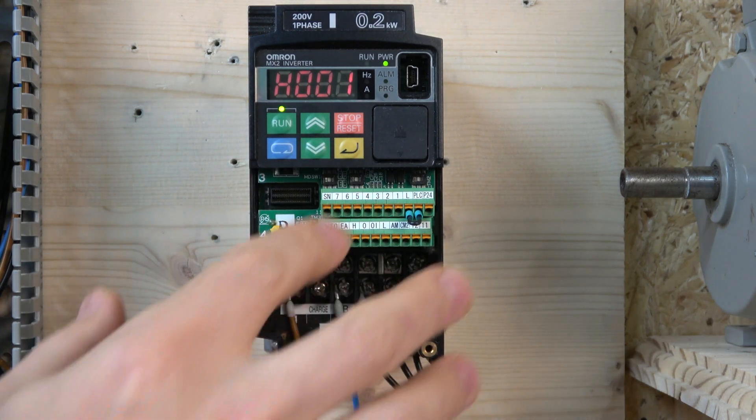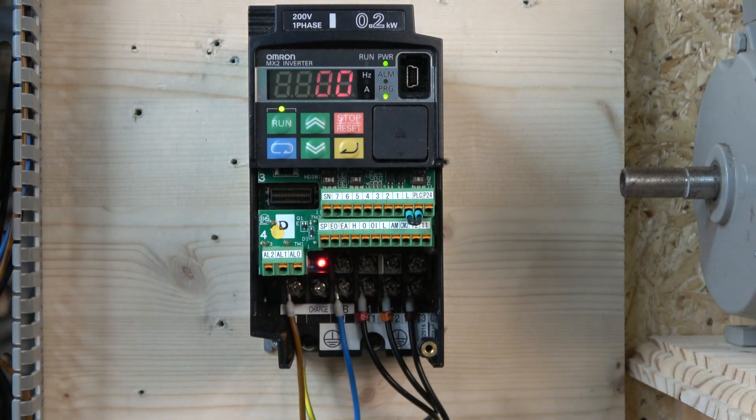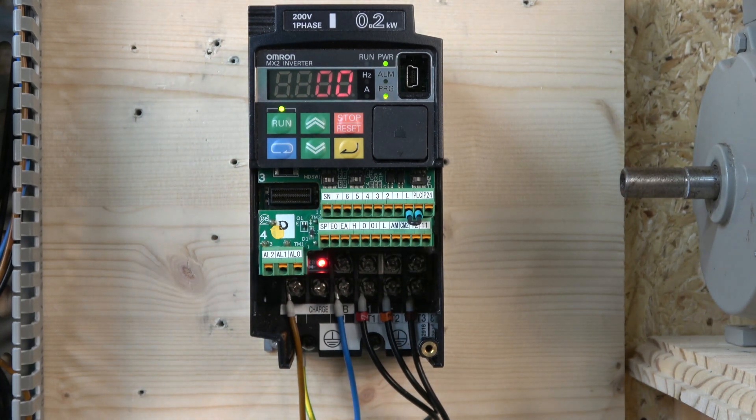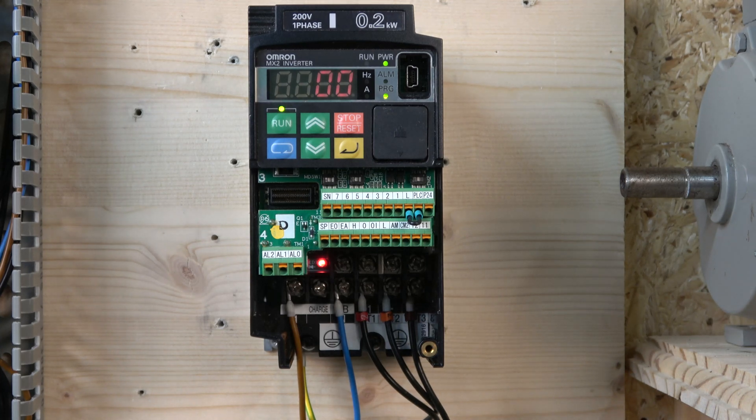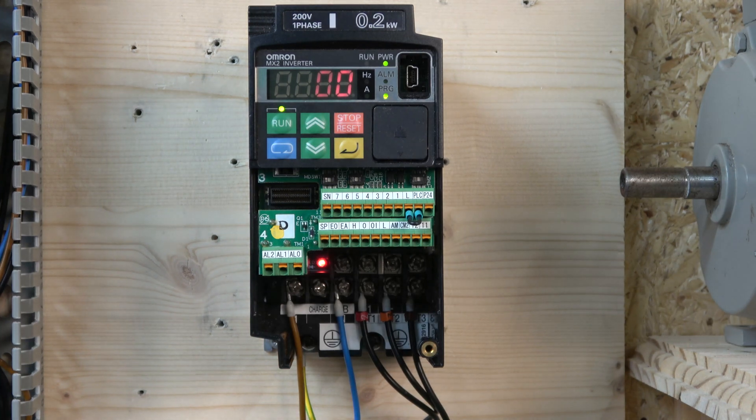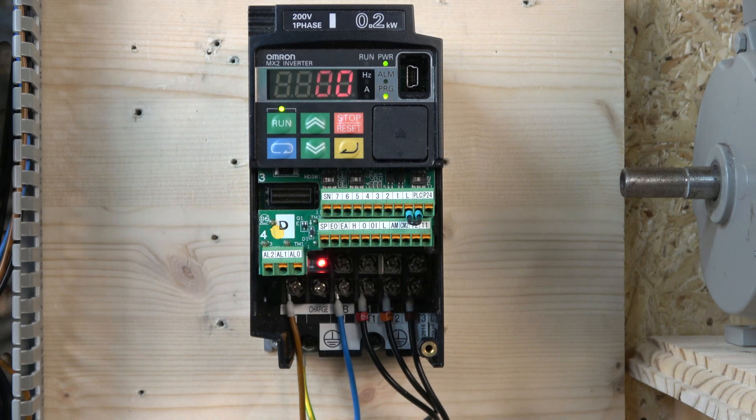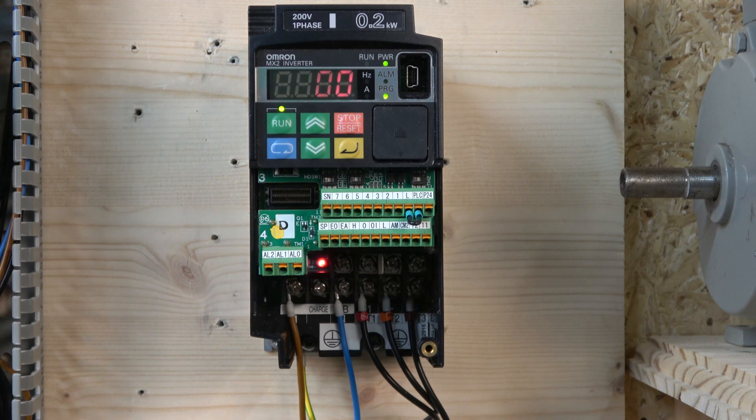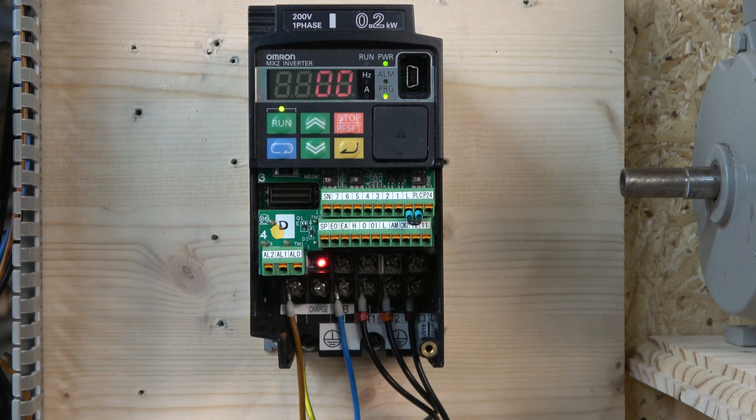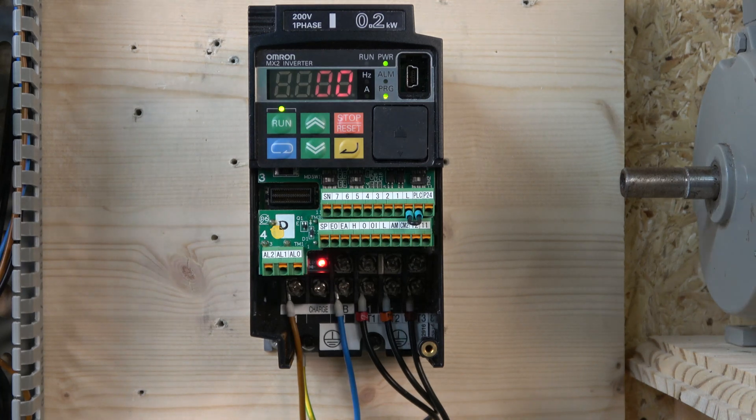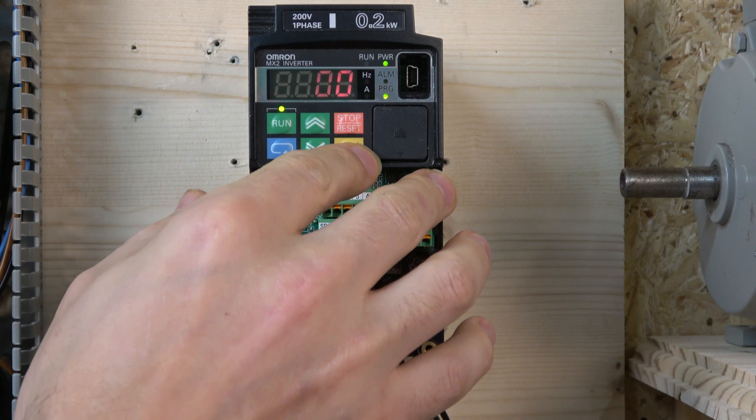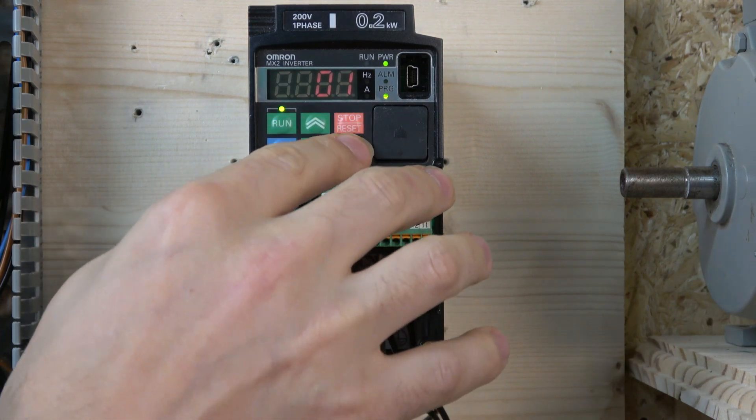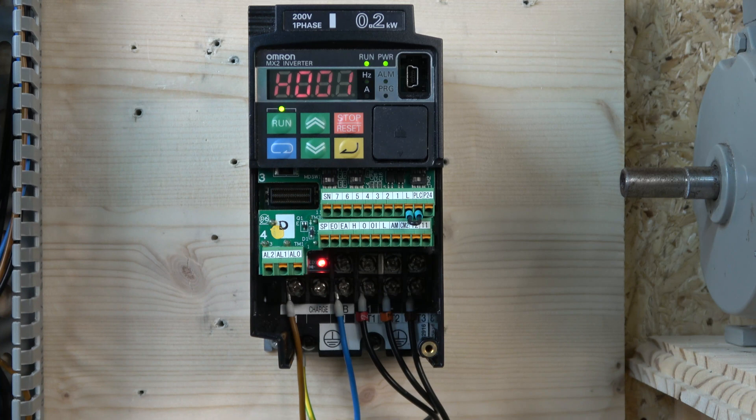Once we've done that, you're pretty much ready to go. Then you need to go to H01. In H01, you select what sort of auto-tune you're going to have. Option 01 is for stop, basically non-rotational. Option 2 is for rotational. I would only suggest doing rotational if your motor is free of any loads. We're going to do 01, which is non-rotational, because in many cases that's what people will be doing. It's also a lot shorter. Let's enter 1 and click the run button, and you're going to start hearing noises coming out of your motor.